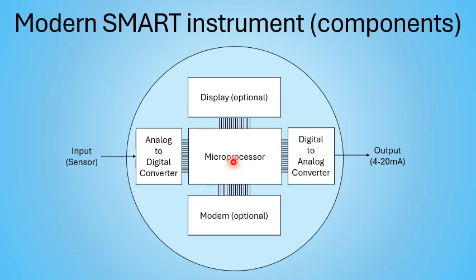The microprocessor is the brains. The microprocessor will do all the math and calculations and all the diagnostics, determinations, etc., all the scaling, filtering, you name it. We'll send that to the digital to analog converter that actually provides the 4 to 20 milliamp output. A lot of instruments will have an optional display as well. We'll talk about that. And a lot of them have a modem for your 4 to 20 milliamp HART signal and so forth, which would actually then talk to your digital to analog converter. Or sometimes you have different communications like Foundation Fieldbus where you don't even have a 4 to 20, it just comes out of the modem. And then we'll talk about the detailed operation of this in the next slide.